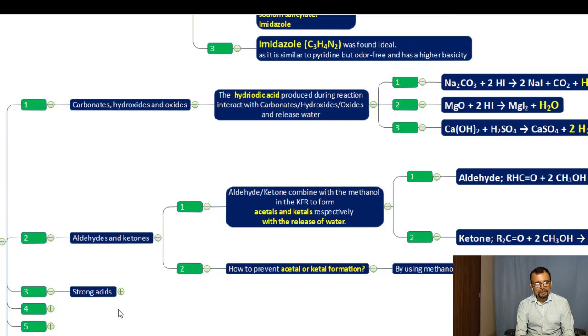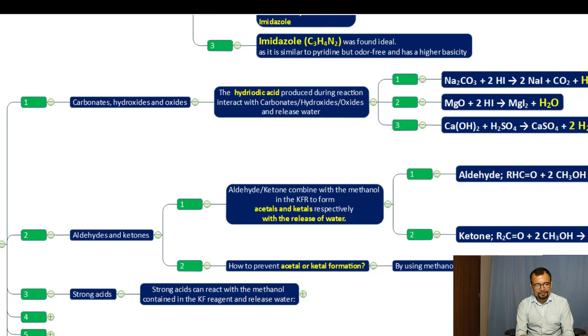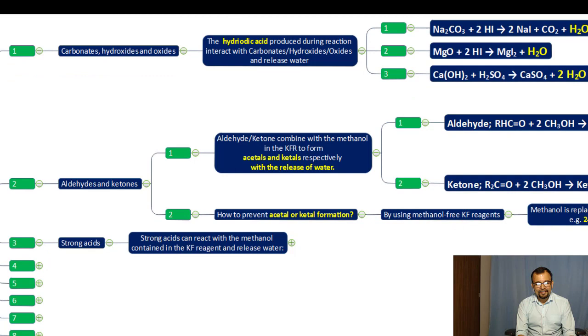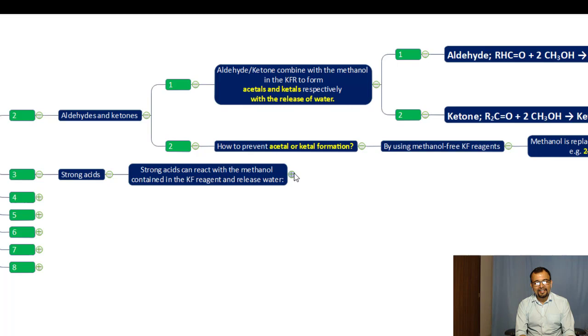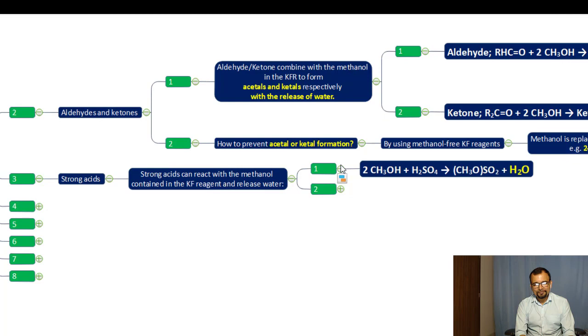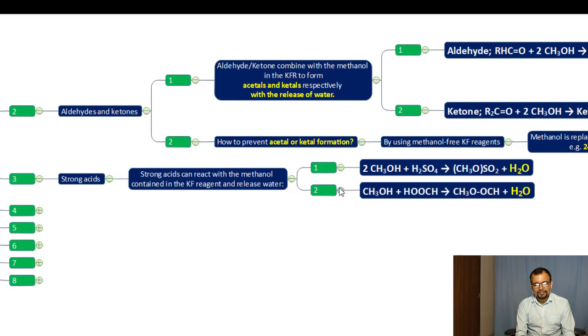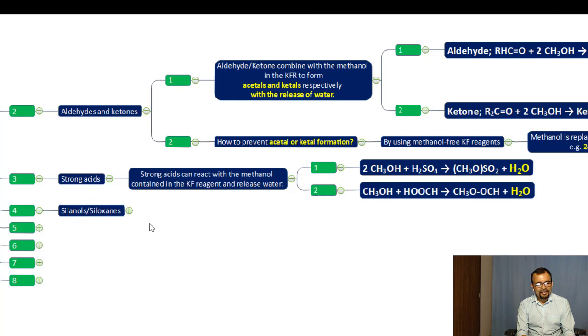The third side reaction involves strong acids. Strong acids can react with the methanol in the KF reagent and release water. For example, sulfuric acid (H₂SO₄) reacts with methanol and releases water. These are examples of strong acids that make the KF reagent unsuitable for determining their water content.